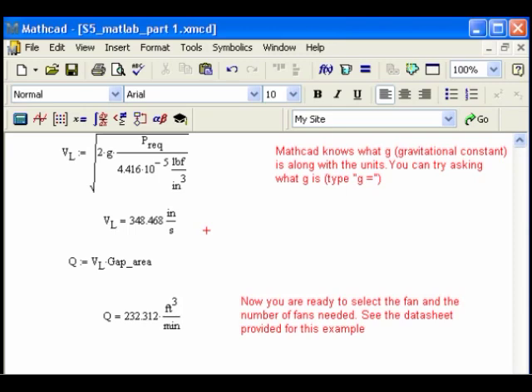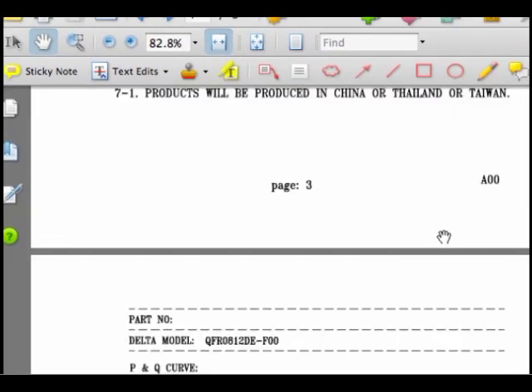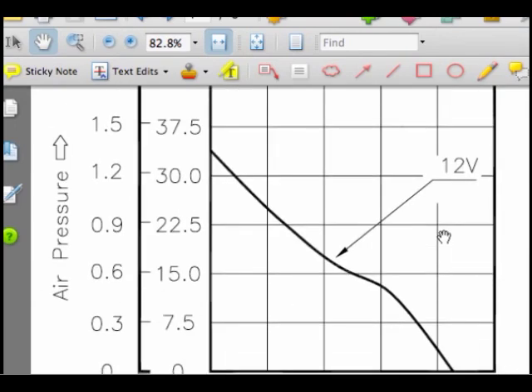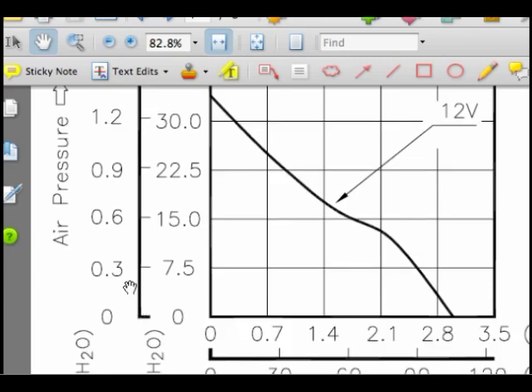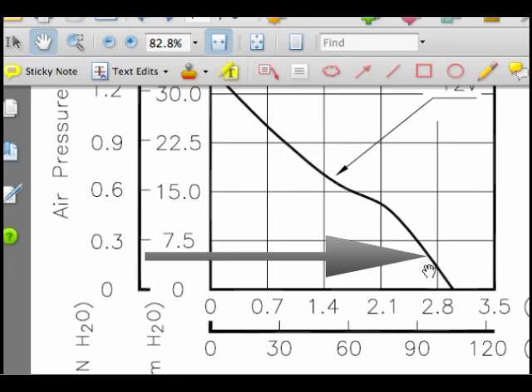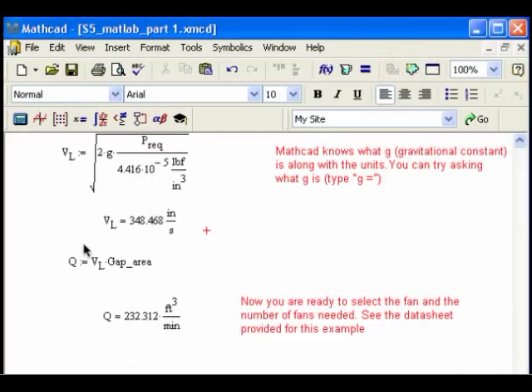So I go in there and I've got to pull in my data sheet, so I open up my data sheet here. My data sheet tells me this graph, and so it tells me I need at 0.192 inches of water, which is this vertical axis here. I come across and read across, I see what intersects my curve, and I come down, and it tells me it's about 95 CFM. So that's the CFM I can get at the desired pressure. And so I need 232, and I can get 95 per fan, so that tells me that I need three fans.